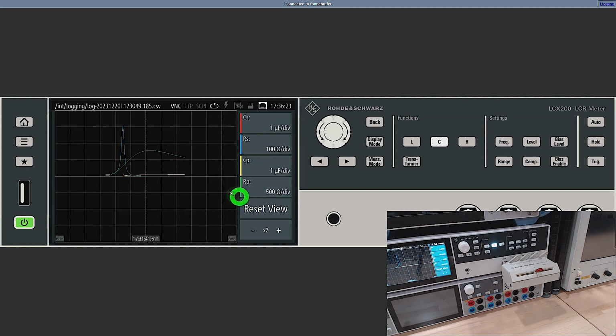And here the sweep is completed, and you can clearly see that there is a resonance discoverable by looking at the parameter RS. If you look carefully, there's a tiny little red line over here. That's the parameter CS, which doesn't mean much in this particular case, similarly to CP. That's why I wanted the auto function. Now I can't quite decipher what this text at the bottom means. Is that the frequency range? Either way, this definitely can be improved. I can zoom in a bit more, and I can move that a little bit further so we can look at the center and where that is, but there are no cursors.